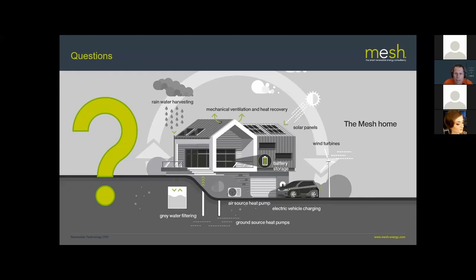Richard asks: for retrofit radiator applications where you upsize radiators, is there also a consideration of pipe lagging to minimise wasted heat on pipe runs? Yes. Also consider domestic hot water recirculation — any heat lost in the recirculation line has to be picked up again by the heat pump. Another place to consider is where lots of pipes return to an underfloor heating manifold, as you may need to insulate those pipes to avoid a local hot spot around the manifold.